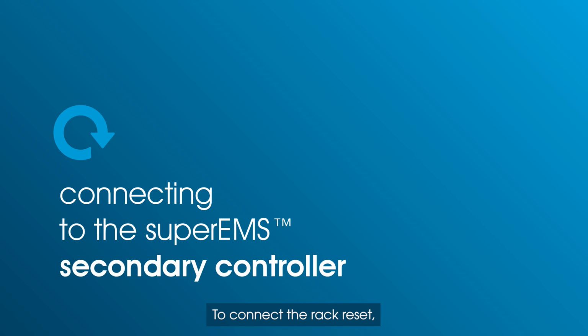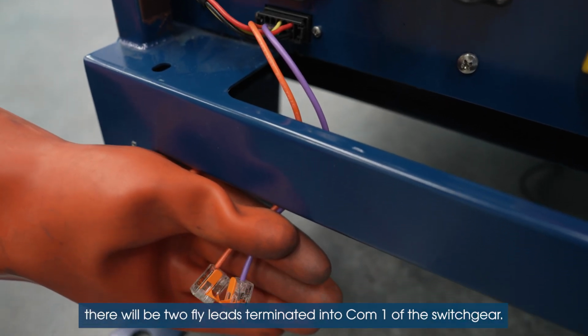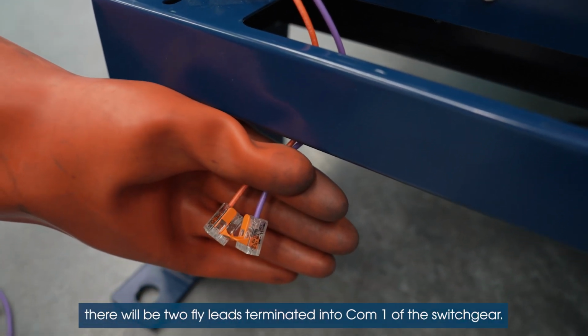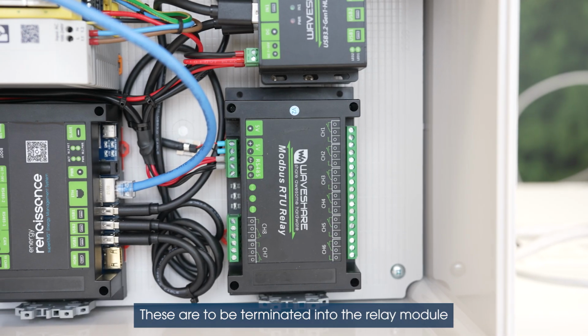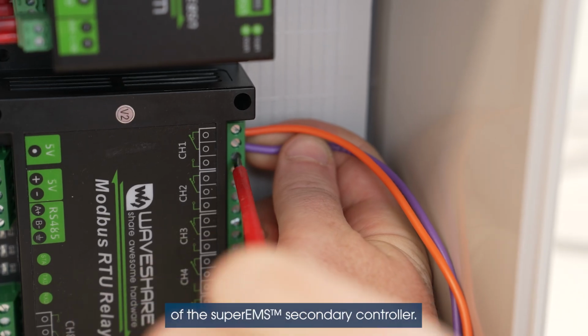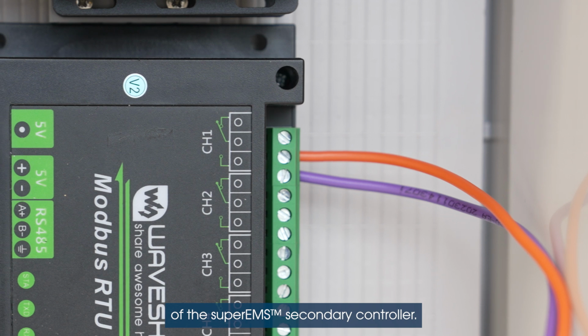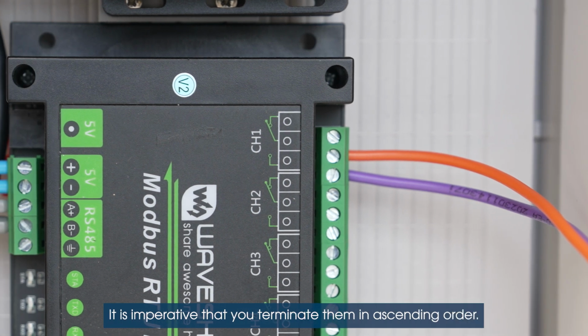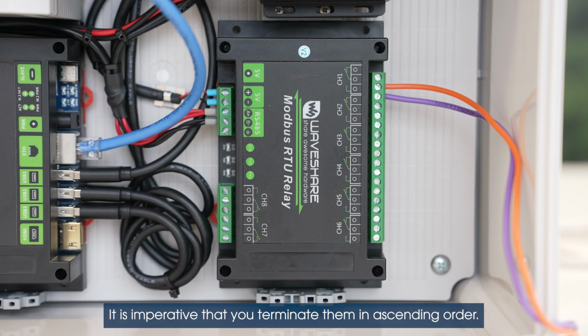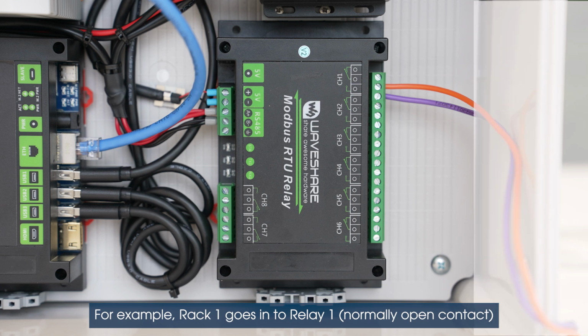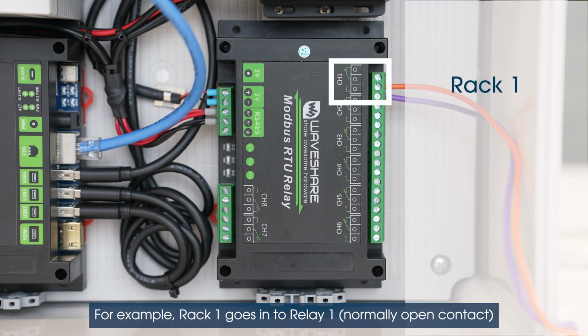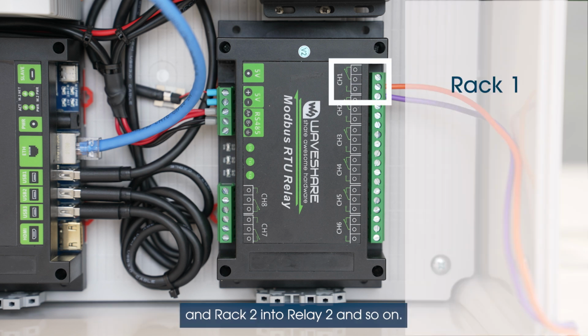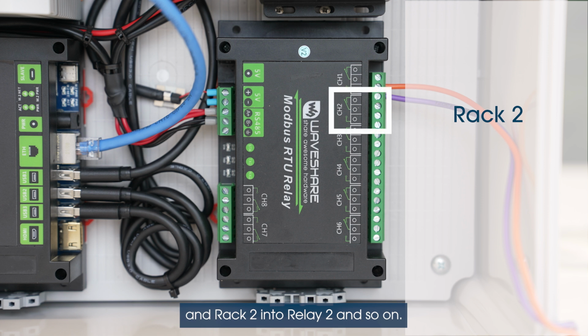To connect the rack reset, there will be 2 fly leads terminated into COM1 of the switchgear. These are to be terminated into the relay module of the superEMS secondary controller. It is imperative that you terminate them in ascending order. For example, rack 1 goes into relay 1, normally open contact, and rack 2 into relay 2, and so on.